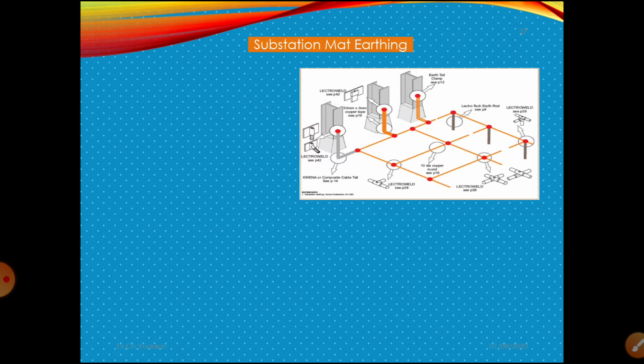By providing mat earthing, the parallel paths increase, resistances are connected in parallel, and the overall resistance is further reduced. This is required to pass the leakage current.